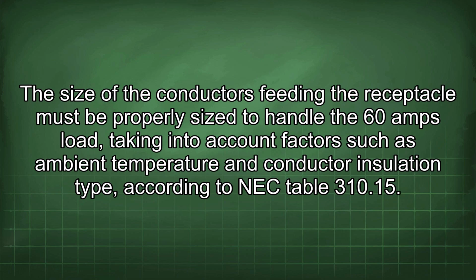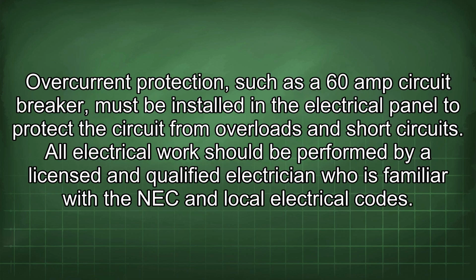The size of the conductors feeding the receptacle must be properly sized to handle the 60 amp load, taking into account factors such as ambient temperature and conductor insulation type, according to NEC Table 310.15. Overcurrent protection, such as a 60 amp circuit breaker, must be installed in the electrical panel to protect the circuit from overloads and short circuits.